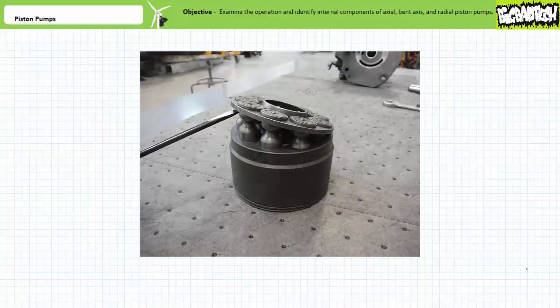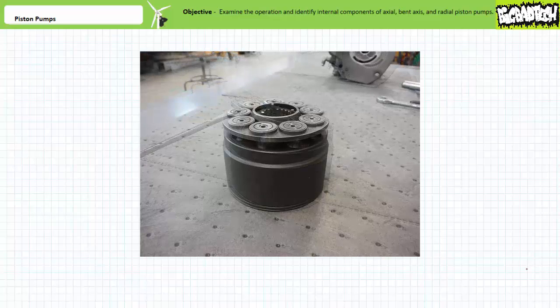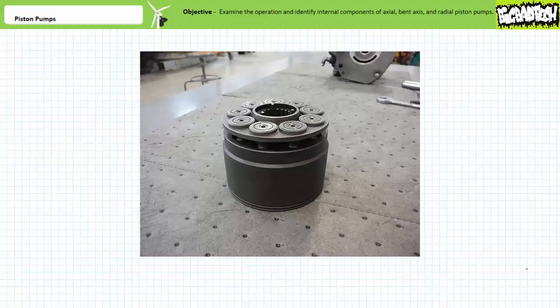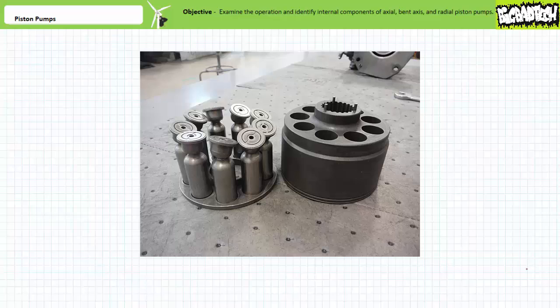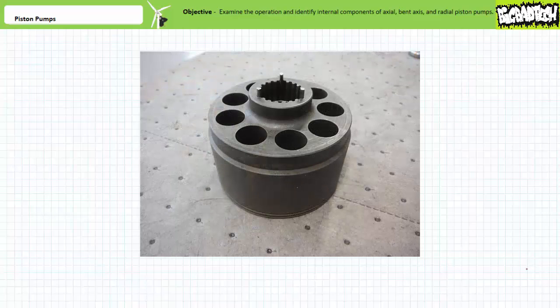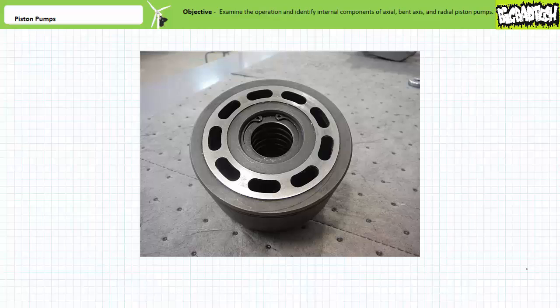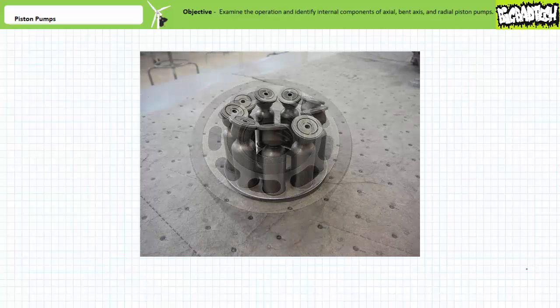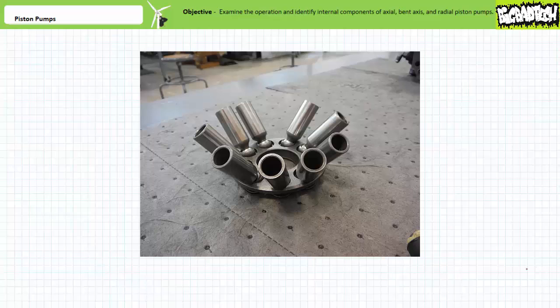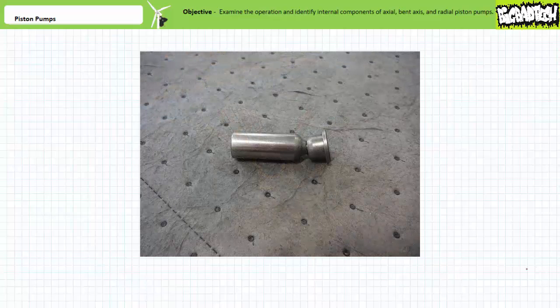Here's the pistons and piston block. When the swashplate is held at a maximum angle, a volume differential exists and flow is at a maximum. When the swashplate is held flat, no volume differential exists and flow is at a minimum. We can remove the pistons from the piston block. Note the ball and socket mechanism allows the pistons to swivel with respect to the swashplate and still reciprocate axially inside the piston block. Here's an individual piston removed from the carrier.